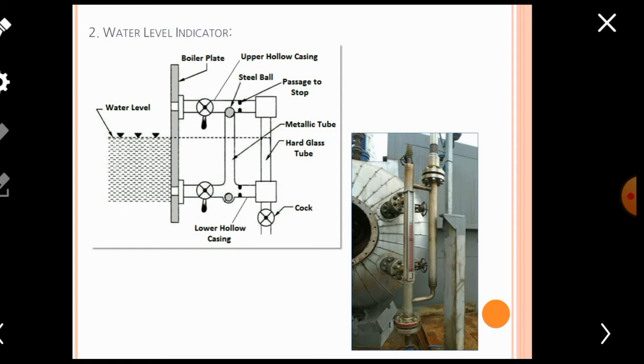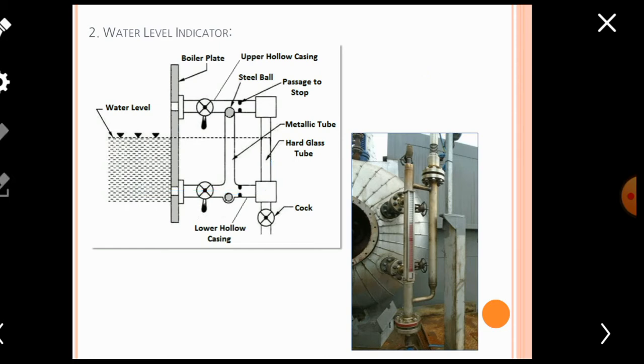Now for the working principle: to measure the water level present inside the boiler shell, first open the steam valve and water valve respectively. This creates an open circuit between steam and the glass tube, and between water and the glass tube. High-pressure steam moves through the horizontal steam tube and reaches the glass tube, while water from the horizontal water tube also moves and reaches the hard glass tube. Since glass is transparent, one can easily find the water level inside the glass tube, which is a parallel indication of the water level inside the boiler shell.